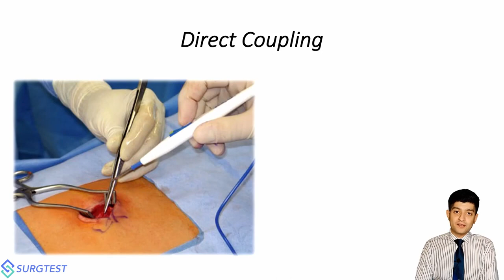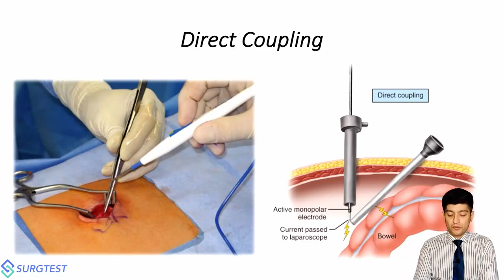Direct coupling is utilized in monopolar energy to our advantage, but in laparoscopic energy, that sometimes happens to our detriment. If you fire your laparoscopic hook or spatula or Maryland forceps when it is beyond your surgical field, you may end up inadvertently touching one or the other ports and causing damage there as a result. Or even worse, you may have that metal trocar then coming into contact with some visceral structure and end up burning that. So direct coupling is an advantage in open surgery, but a very, very problematic issue in laparoscopic surgery.